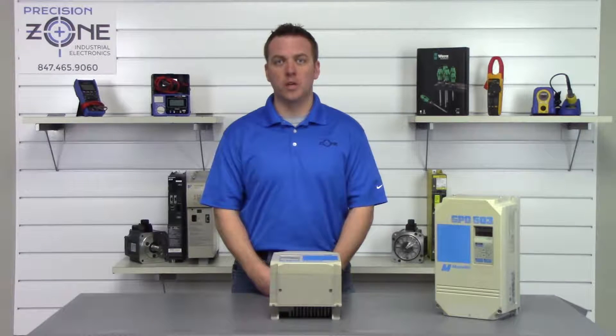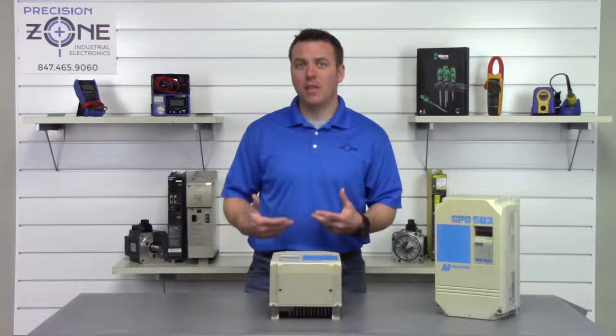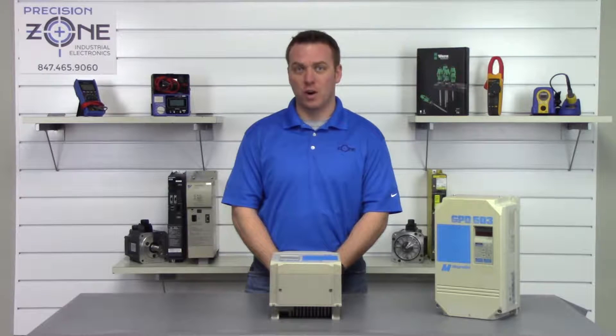If you're getting overload alarms, you'll want to verify that the conditions the motor is in are in good working condition and that the cooling is working properly to the motor and the drive.